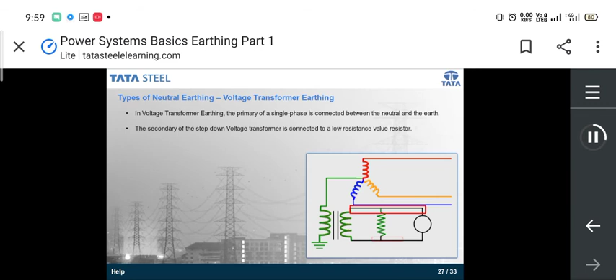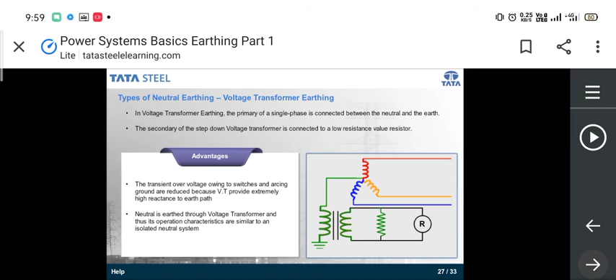The transient overvoltage owing to switching and arcing ground are reduced because the voltage transformer provides extremely high reactance to the earth path. Next, the neutral is earthed through the voltage transformer and thus its operation characteristics are similar to an isolated neutral system. Well, this was about voltage transformer earthing.